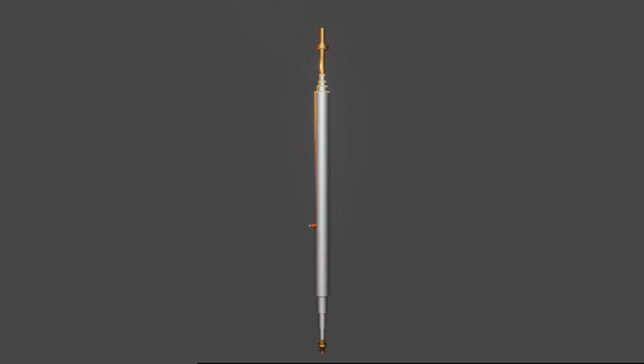This is the tan delta terminal projected from the outermost aluminum foil of the condenser system of the bushing. Here some insulation is provided. Why have we provided this insulation? Actually, this insulation isolates the tan delta terminal, that is the outer aluminum foil, from the metallic flange. Here, we remember that we connect an aluminum foil below the outside capacitor, not the outermost capacitor foil, although we have shown the outermost layer in our demonstration as grounded. In practical cases, the metallic flange is externally connected with a short piece of conductor to the tan delta terminal, so that this aluminum foil always remains at earth potential or zero potential.